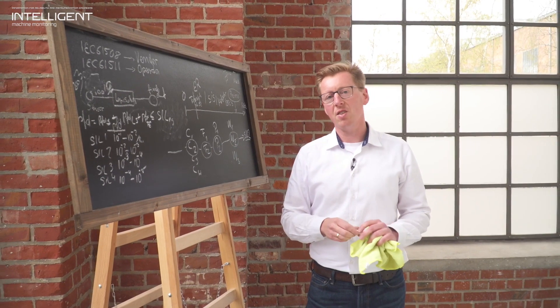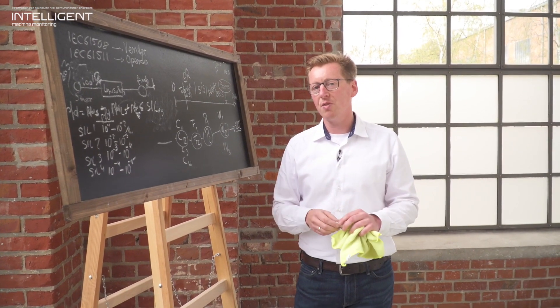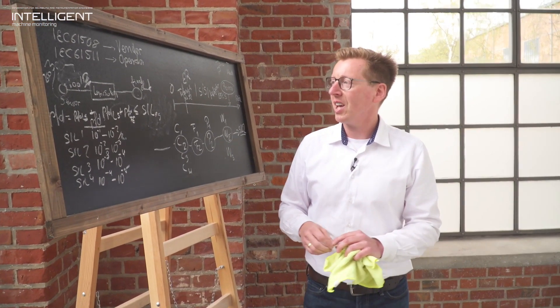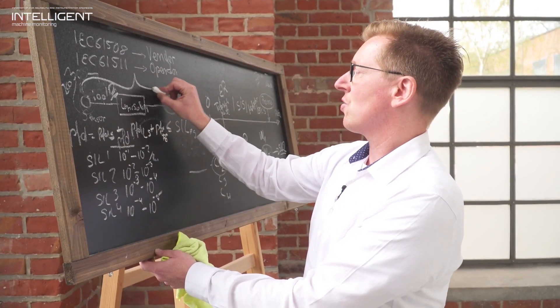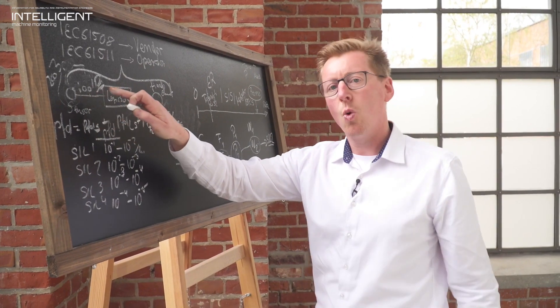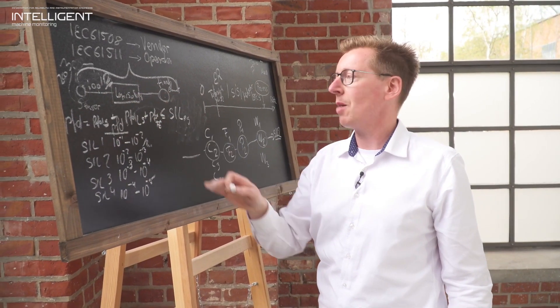Another way to reduce the PFD that you have within your system is to increase the number of proof testing intervals. So you increase the frequency of testing your system. In this case, you have to test the entire safety instrumented system to make sure that it works as intended for this application.